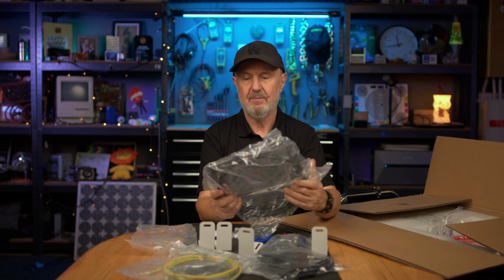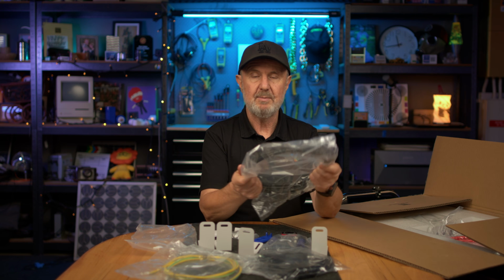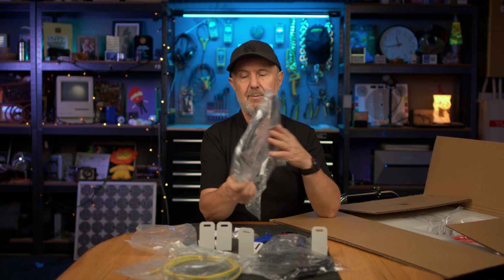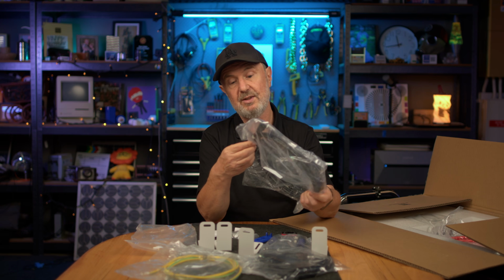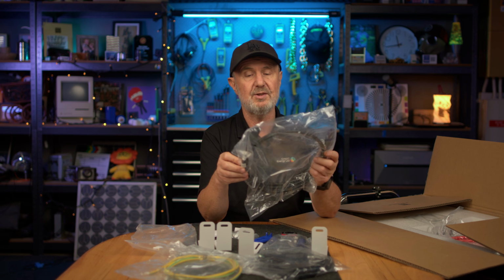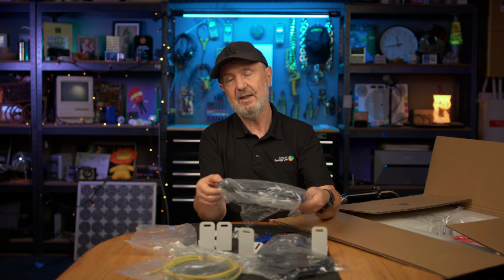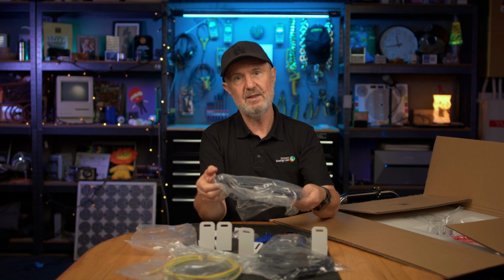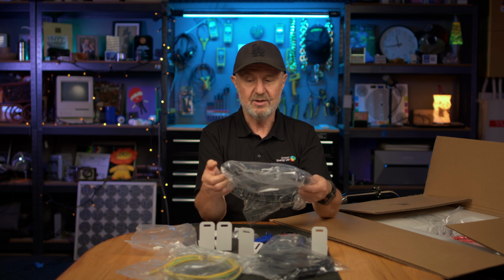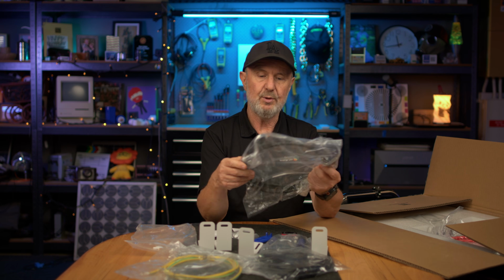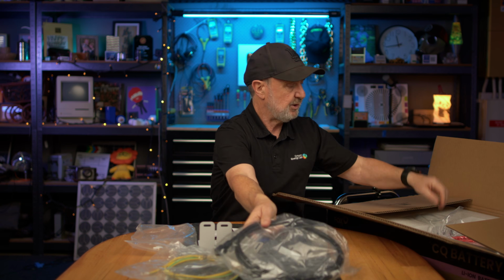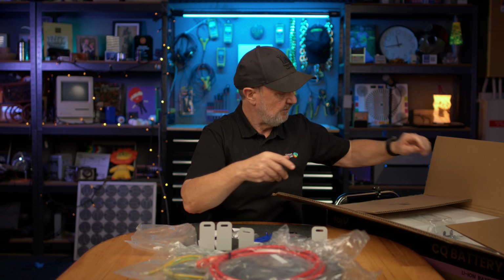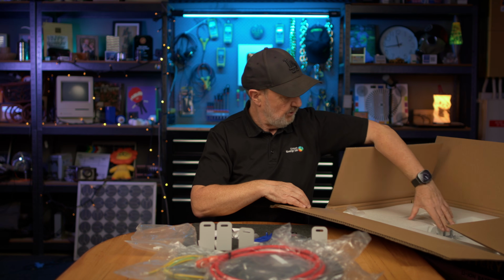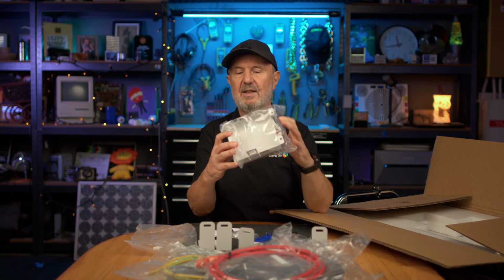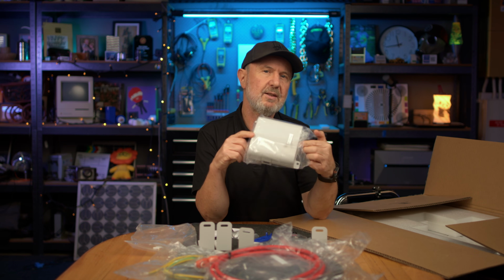And some nice big 16 millimeter cables here. These are 90 degree rated cables, 16 millimeter cross-sectional area with locking connectors, so they can't be disconnected without knowing what you're doing. There's a little button on the side you've got to push in. And of course, they'll be protected by a very important part of this whole kit, which is a cover that goes on the side of the top unit.